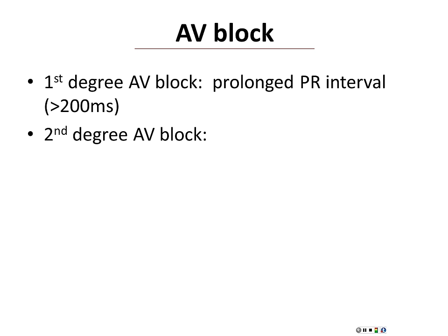Keep in mind, as soon as you flip this down into pacing mode, it is in pacing mode. So if it does not see a QRS complex at the rate that it is set, it will start pacing. There's no on/off. You can't have it on standby. Once it's in the pacing mode, if it doesn't see a QRS, it will pace. You can just play with these dials to change the rate, which will appear on the bottom of the screen, and to increase your milliamps until you get capture.